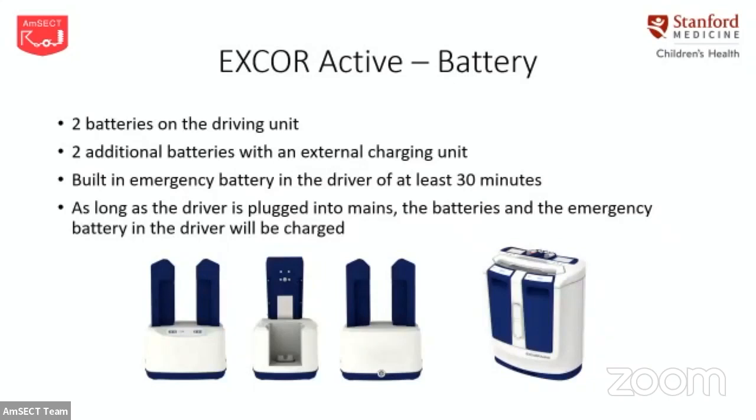So we'll talk about the battery first. If you can look on the bottom right, you'll always have 2 batteries inserted into the driver itself. And then each patient also gets 2 additional batteries with a charging unit. And in the driver, there is an emergency backup, again, a minimum of 30 minutes with that. And as long as you have the driver plugged into wall power, you are going to be charging the batteries that are inserted in it and the emergency battery.